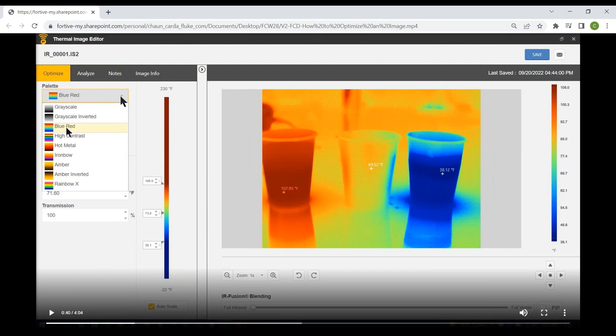Right now I'm using the Blue-Red palette because red means hot and blue means cold — universal color connotations — which makes the chart simple to understand. Remember, palette is simply a color scheme; the color tones correspond to the apparent surface temperatures of the target. Slight differences are easier to see with monochromatic scales like gray or amber. High contrast palettes make it easier to quickly find obvious anomalies. Most customers I work with prefer the Ironbow palette, but you should select the palette that best works for your image.